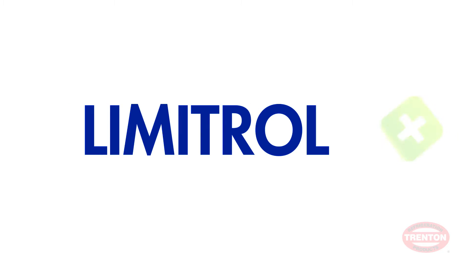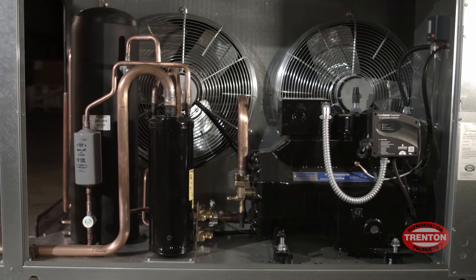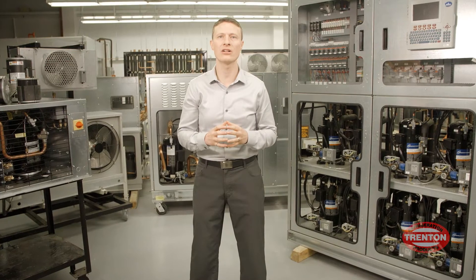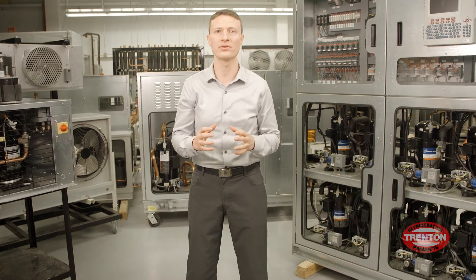Together, they achieve the best results every time. Limitrol Plus saves both energy and refrigerant, and is designed to work in the extremes of the North American climate. Our award-winning Limitrol Plus combines variable-speed EC motors, condenser portioning, and other system modifications to provide the ultimate in performance and control. These technologies combine into a responsive system that floats head pressure, saving refrigerants and energy up to 30%.